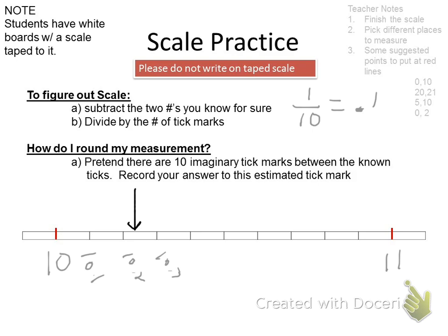So, first of all, we note that this instrument is measuring one place past the decimal, or to the 10th spot, which means we're going to make up an estimate for the 100th spot when we measure. So for example, we could look at this and agree that we all know it goes to at least 10.2. 10.2 should be undebated.